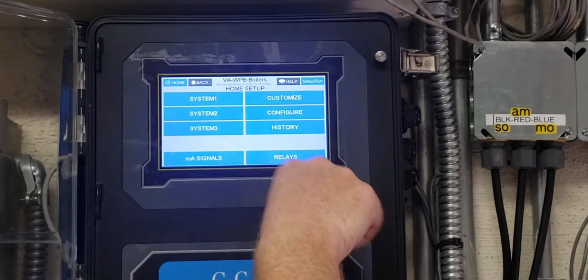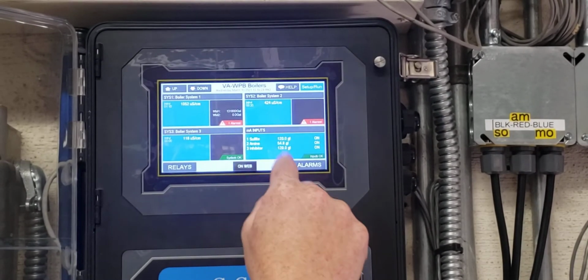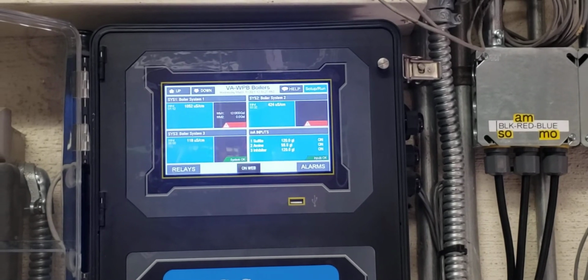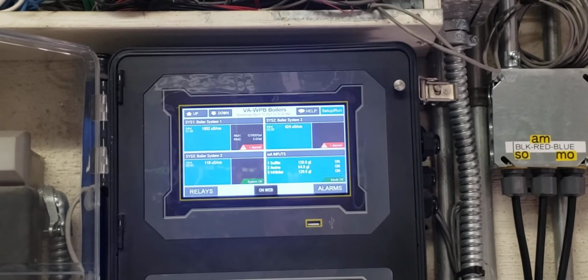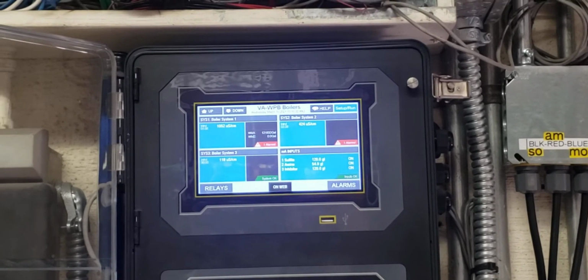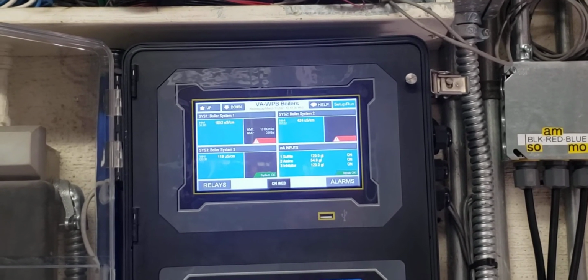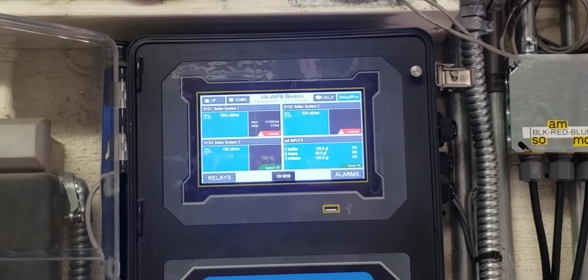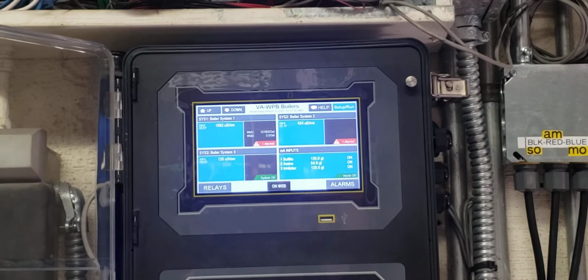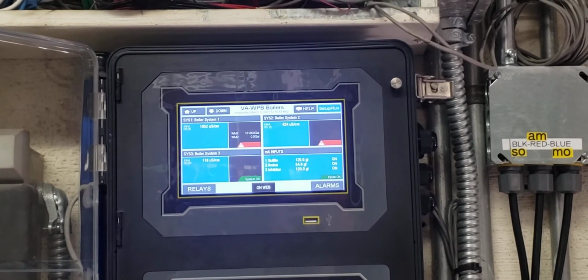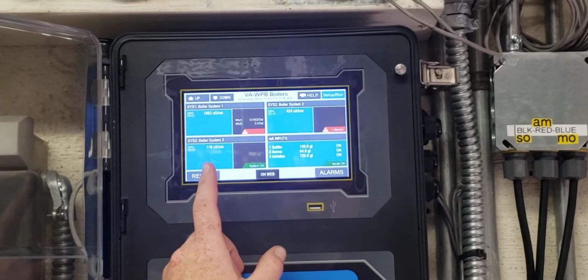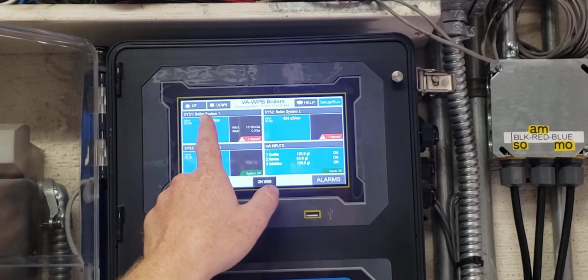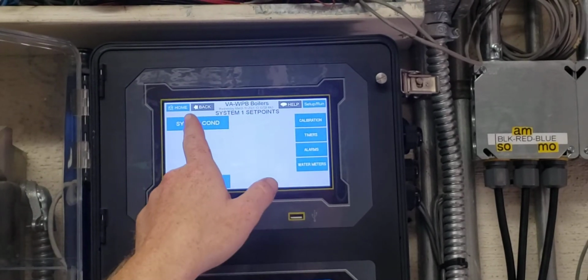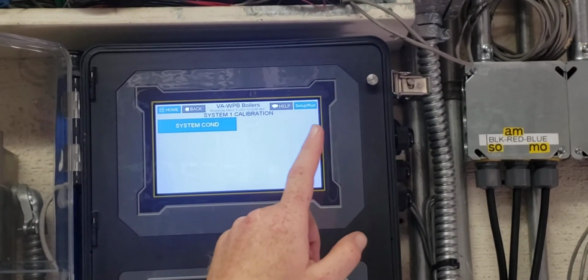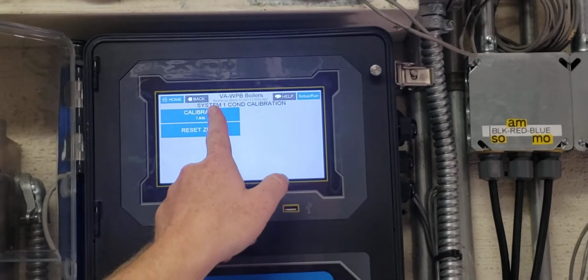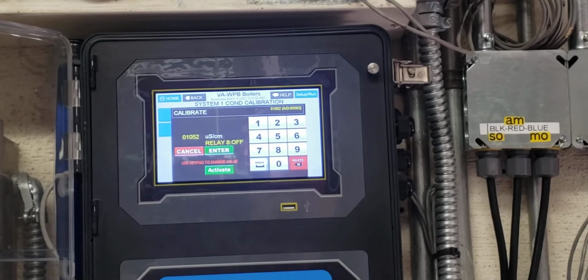Let's go over doing a calibration. Say you come in and the sample you got over there was way off, like 300 microsiemens off. If it's 200 or whatever, that's okay. But anything more than 300 to 500 off from the reading you got in the logbook is where I want you guys to come into the controller. You can go to calibration for system 1, conductivity, calibrate, and you literally can just type in what you got.